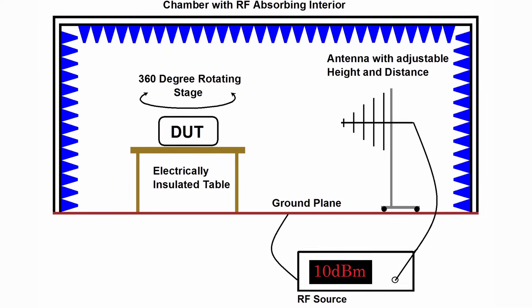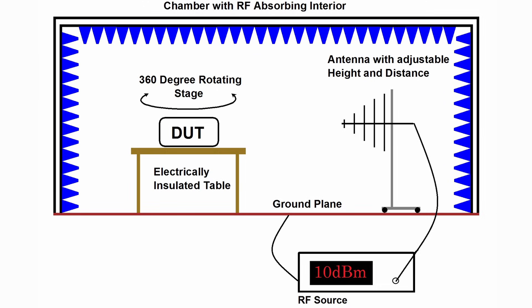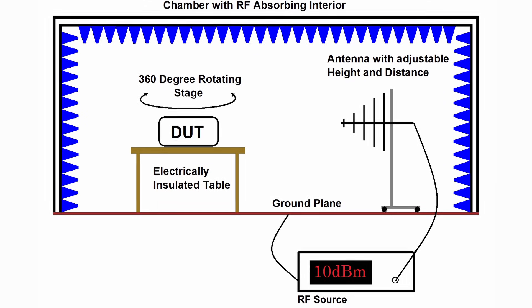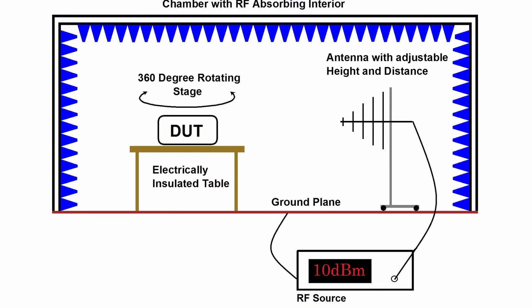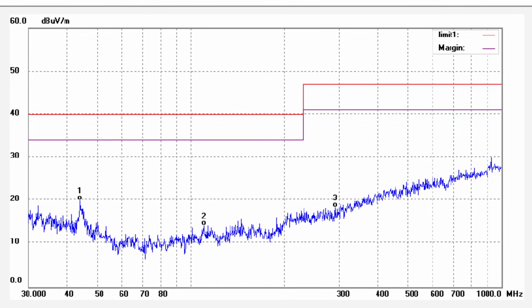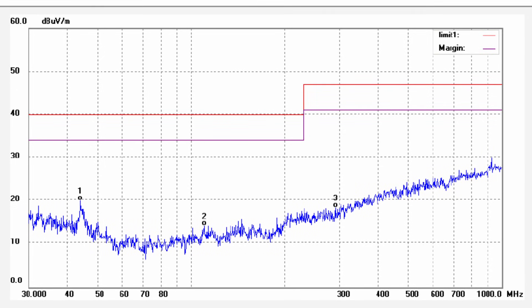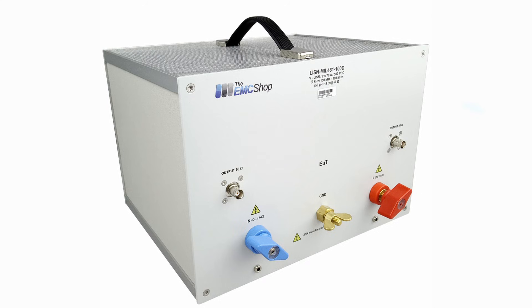With radiated emissions testing, there is a calibrated antenna positioned a specific distance away from the device under test — usually 3 meters or 10 meters. An automated process adjusts both the antenna's height and polarity to find the maximum emission levels, and the device under test sits on a large turntable that can rotate 360 degrees to measure emissions from all angles. A spectrum analyzer is connected to the antenna to measure and record the emissions data. The regulations call out a specific frequency range to test across — for radiated emissions it is typically 30 MHz up to 1 GHz, but it can be higher depending on the standard.